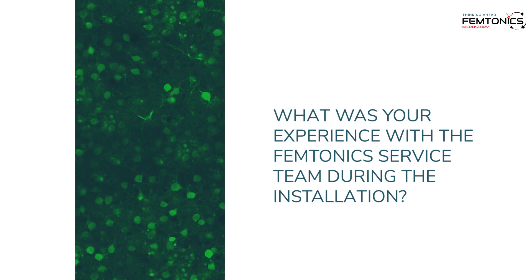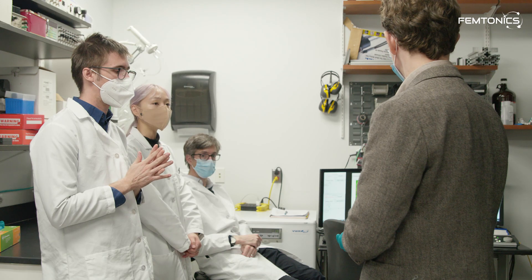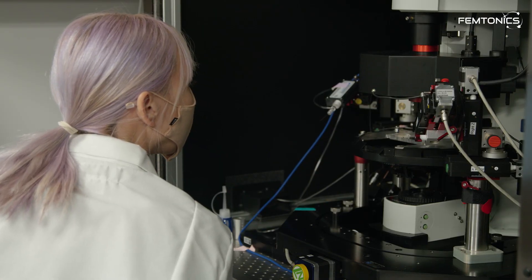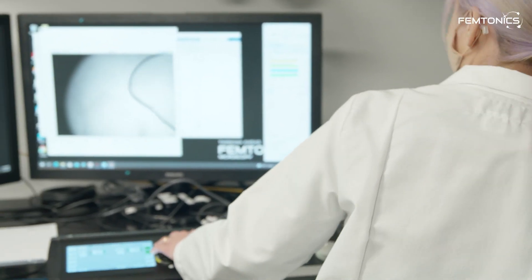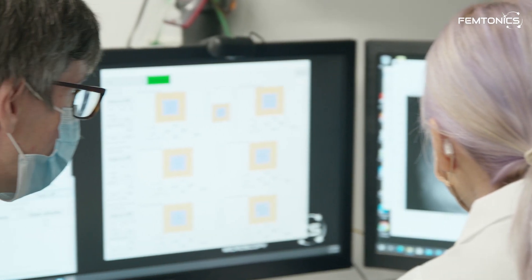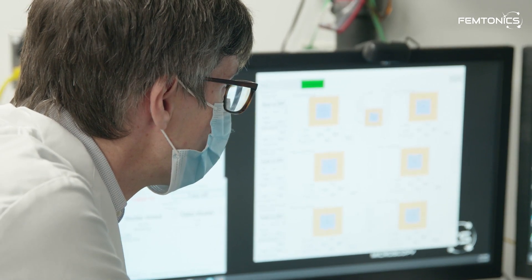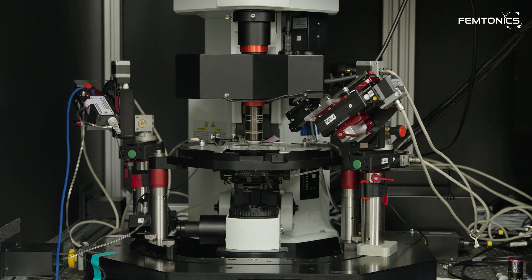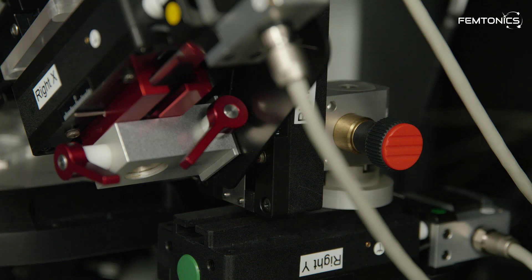What was your experience with the Femtonics service team during the installation? A team came in and helped us assemble the microscope in my lab. Several members of my lab were there to watch the process and help out when they could. With a commercial system, there are a lot of black boxes — things that work but you may not know exactly why or how, as opposed to a system you build yourself from scratch, which is what a lot of people do with 2P systems. Being there for the week building the system with the technicians was really helpful for understanding the various pieces and parts, such as the beam conditioning unit and the AODs.